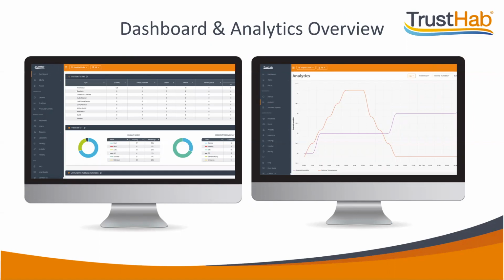On another partner property, an alert for a unit's excessive runtime triggered the maintenance team to check in on that unit's HVAC. The resident had not complained of any issue, but the team went and investigated anyway. Upon inspection, they noticed the coil was completely clogged and frozen. They were able to remedy this issue with preventative maintenance, whereas if it was left to run unchecked, it would have turned into a costly repair.